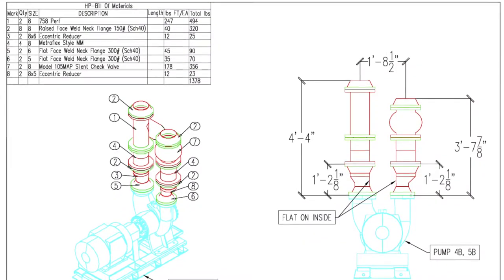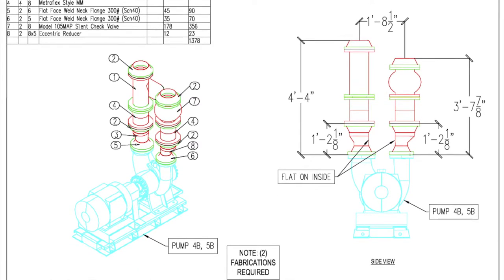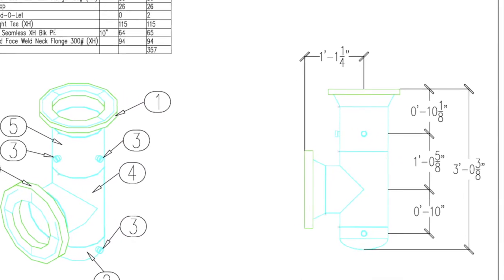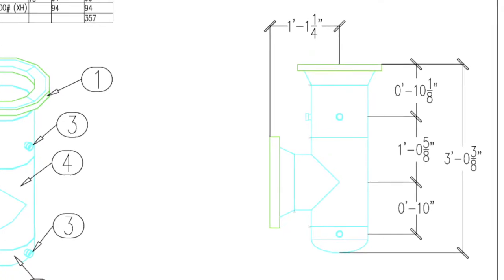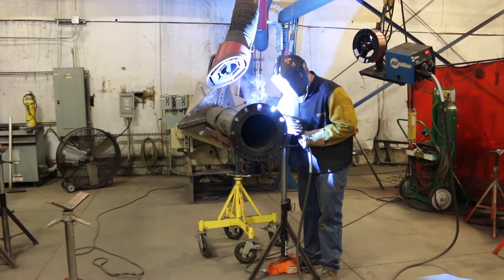The next step is we take that entire model and break it down into smaller module assemblies. We indicate what components make up each spool, such as elbows, pipe, and weights of pipe. We dimension any specific items. Then these spools are provided along with the material stock list to the fab shop where we start the fabrication process.